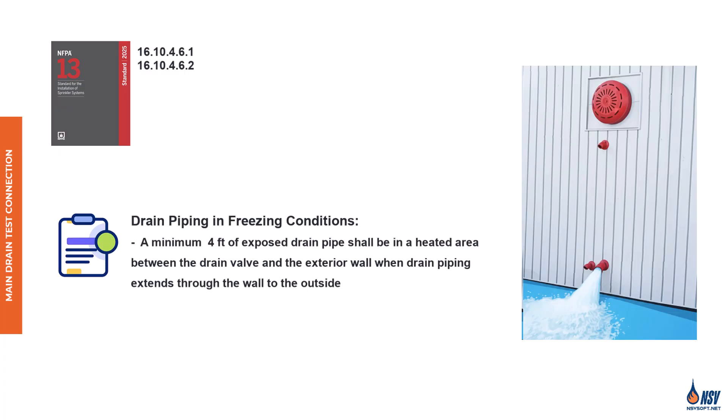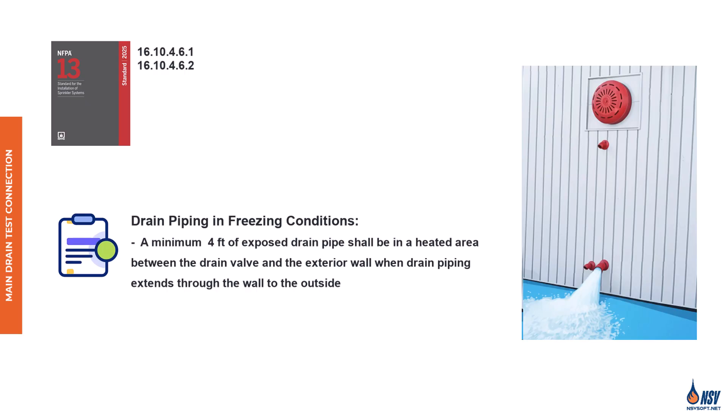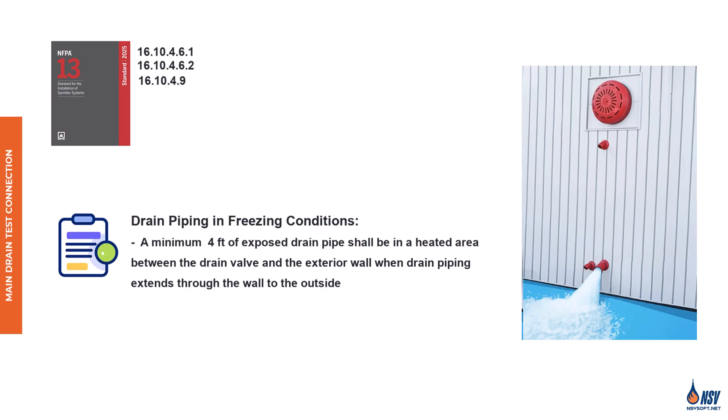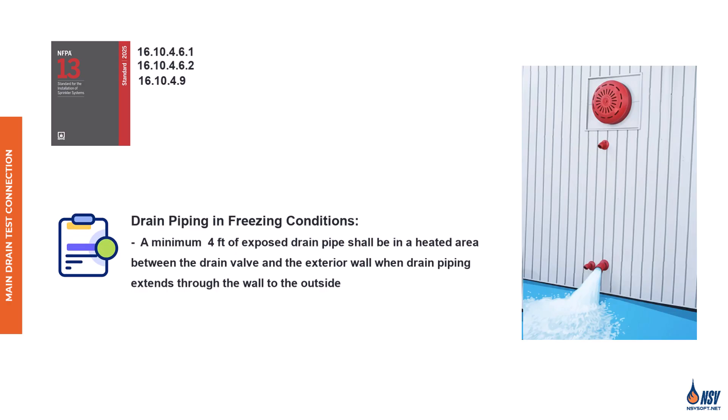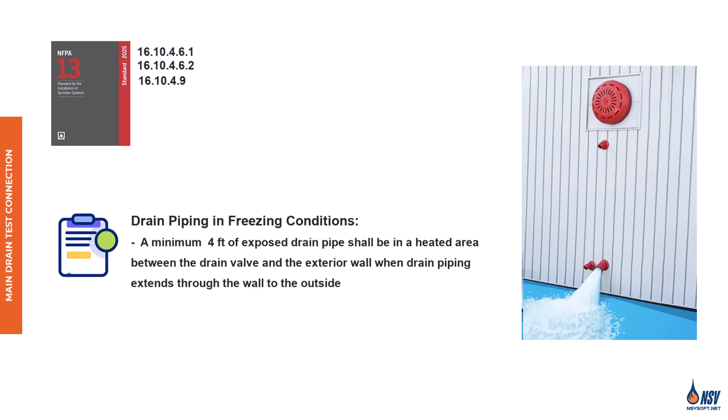When sprinkler systems are installed in areas where the exterior temperature is subject to freezing, special precautions must be taken for the drain piping. According to NFPA 13, 2025, Section 16.10.4.9, at least four feet of exposed drain pipe must be located in a heated area between the drain valve and the exterior wall whenever the drain piping extends outside. This requirement acts as a frostbreak, ensuring that cold air from the outside does not cause the water inside the system to freeze.